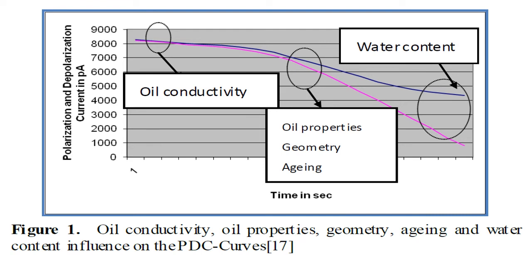At the end of waveforms of the PDC current on the right side, we can check the moisture content in the isolation. More theoretical information you can see in the article in the description of this movie. Because this is only some example, the full picture of this phenomenon, we can see only comparing with such a graph after some time, how the graph will change.